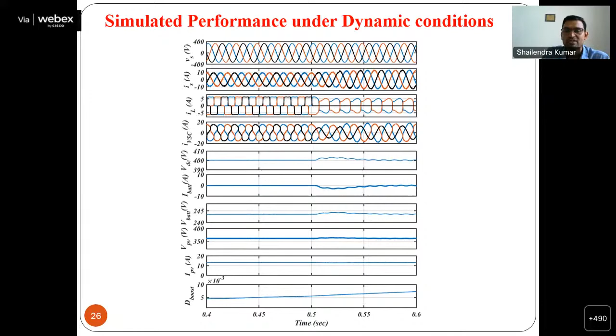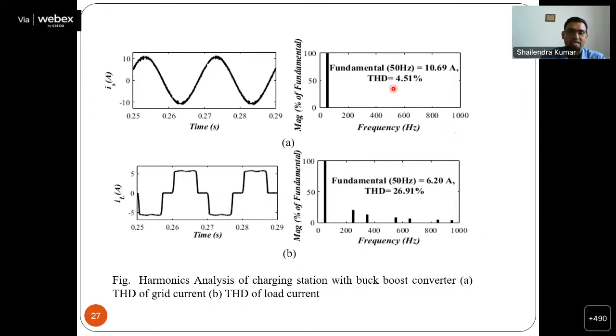And then we also have results when we are doing load unbalancing, because we have to check the charging station performance when the load is unbalanced, as I told you. And for harmonics, here we are maintaining 4.5% THD, and this THD is maintained within the IEEE 519 standard. However, the THD of the nonlinear load, when we have the onboard as well as the nonlinear power-based load, is 26%, which has been reduced directly to 4.5%, less than 5%.